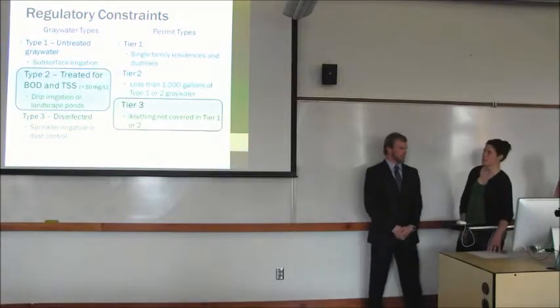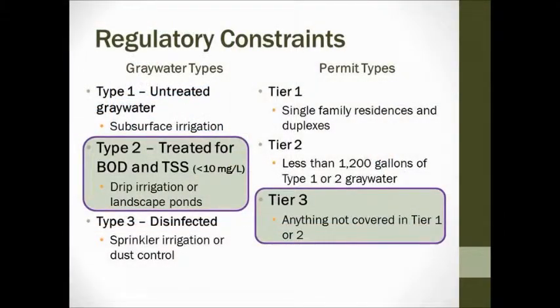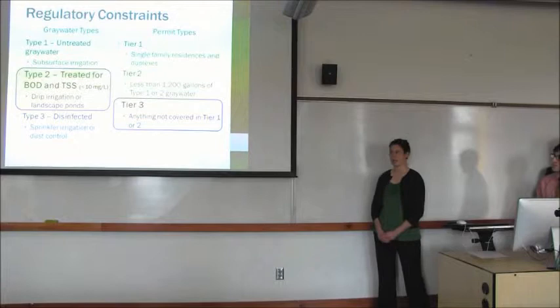Now I'll talk about some regulations. Under Oregon ODEQ regulations, there are three types of gray water. Type 1 is untreated gray water and can only be used for subsurface irrigation. Type 2 is gray water that has been treated so that BOD and TSS levels are below 10 milligrams per liter, and can be used for drip irrigation or landscape ponds. Type 3 is Type 2 that has also been disinfected. Our subsurface treatment wetland will treat to Type 2 gray water. And because the fair is not a residence, we'll be using a Tier 3 permit, which has costs associated with it that Katie will speak to later.